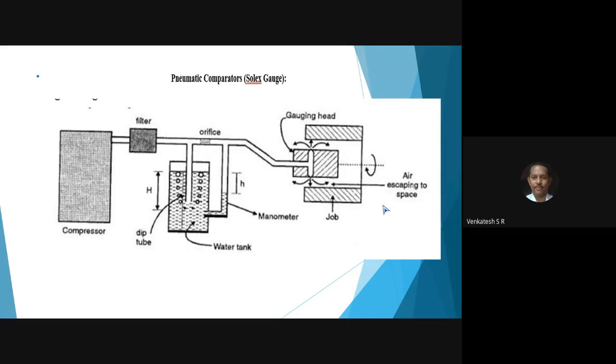Say for this, is the outside diameter important or the inside diameter important for a liner? Say in this case, particularly for a liner, the inside diameter is very, very important. You have to check the diameter of the liner, ovality of the liner, straightness of the hole, and other elements of the hole, which are very, very important.